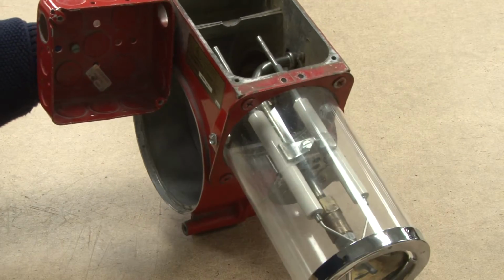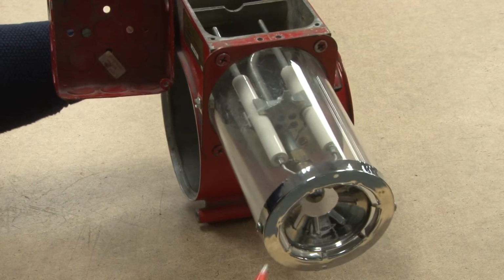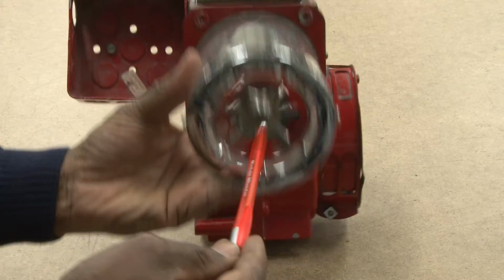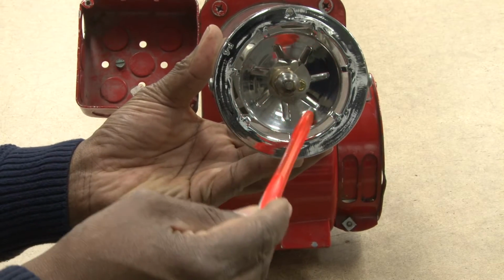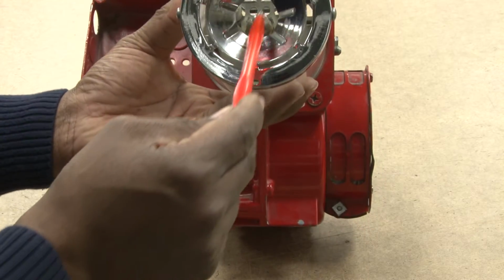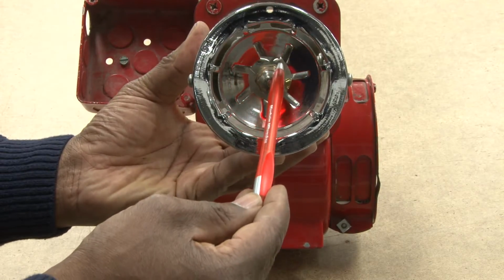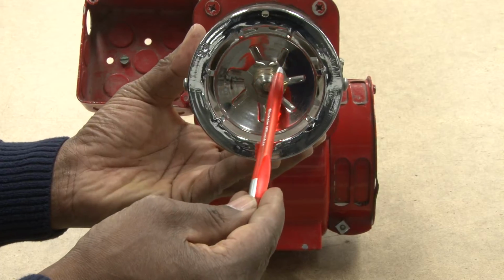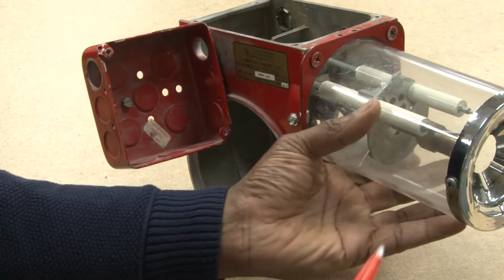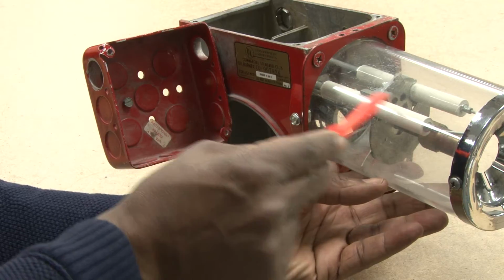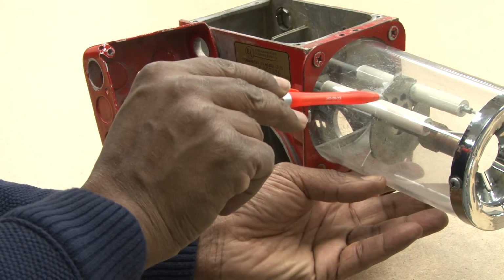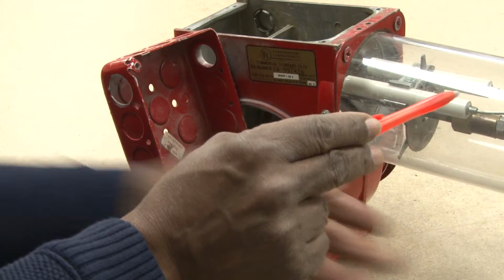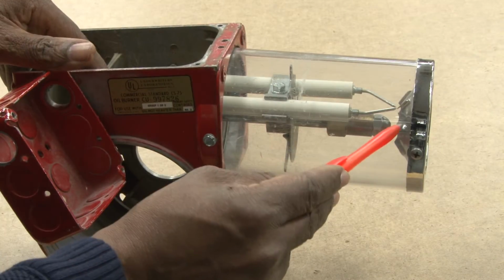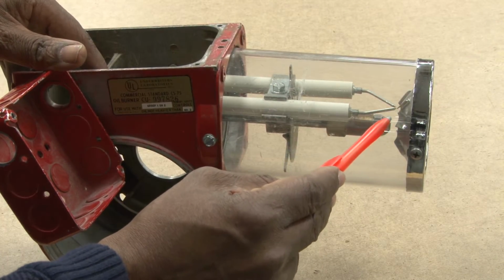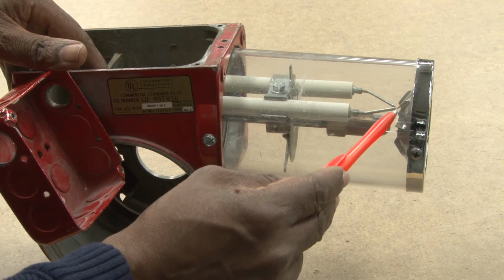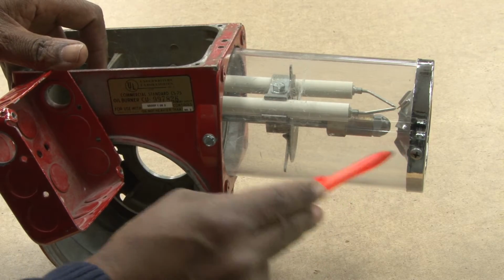I'm going to bring it so you can see a little bit better the retention head with the nozzle in the center of it and the electrodes mounted just on top, these two little small electrodes. To show you again, you can see the ceramic insulating the high voltage electrodes at the tip that are very close together, that would make a very strong spark to light the oil. And the oil would spray just below it.